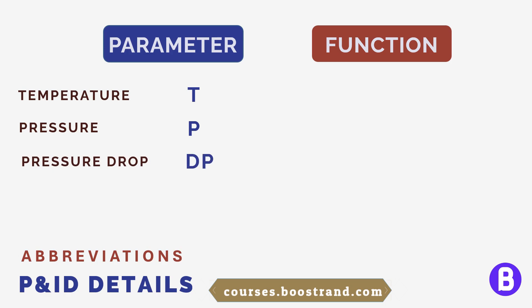For level it shall be L, for flow it shall be F, and so on. If this is a temperature gauge that measures the temperature locally, then the second letter shall be G, so the instrument abbreviation shall be TG.